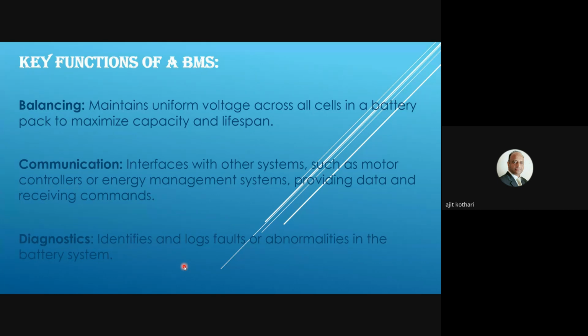Then diagnostics - diagnostic is nothing but identifying the issues in the battery bank, let's say voltage is less or more, what happened to the battery bank. You can go to the logs of the battery bank, which are available in the BMS, and from that you can identify which cell is having an issue, which cell has more temperature. This helps you in rectifying the battery bank - it gives you the complete information, and you can easily detect the faulty cell from the battery bank and replace that cell. That's how you do diagnostics on the battery bank.